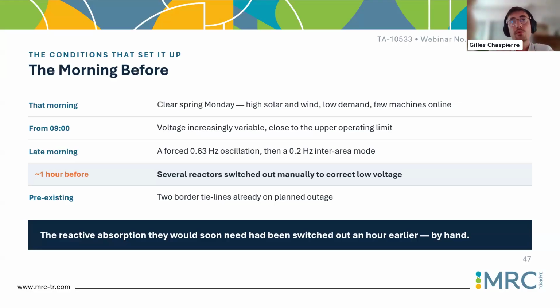And unfortunately, at some point, the voltage reaches an unacceptable value at the point of connection of some units, PV or classical synchronous machines, which tripped because of a bit too thin protection margin, leading to this cascade and acceleration effect that I discussed in the following.